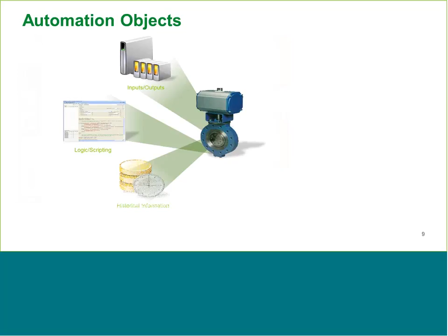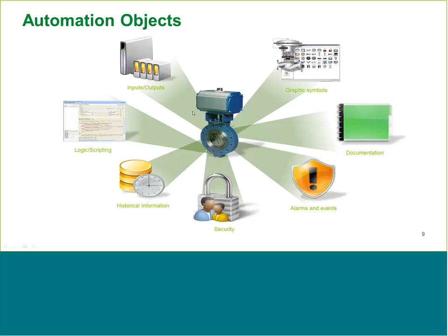Another differentiator with System Platform is we create objects that typically represent a piece of equipment. In this case, I've got an example of a valve. My valve object would include where the I/O is coming from, where my controller is, any graphics associated with this valve, any alarms and events, security for who has access to this valve in terms of development and runtime operational permissions, and historical information. If I want to add a valve attribute to my historian, I literally just check a box and it automatically adds a tag to the historian, as well as any logic or scripting associated with this object.